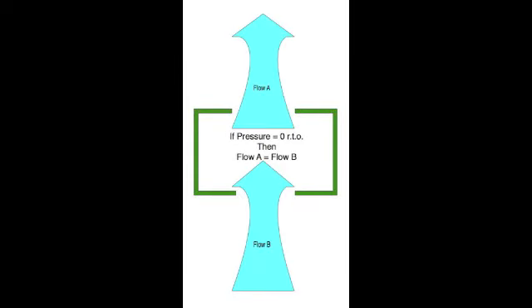Now imagine air naturally moving into and out of the box. If the pressure inside the box is zero relative to outside, you can rest assured that the airflow coming into the box is equal to the airflow coming out of the box. In other words, flow A equals flow B.